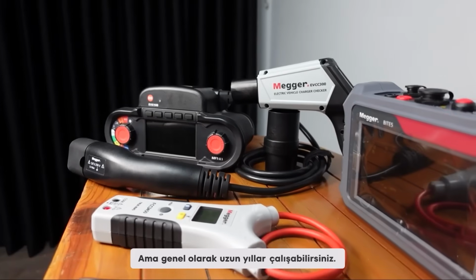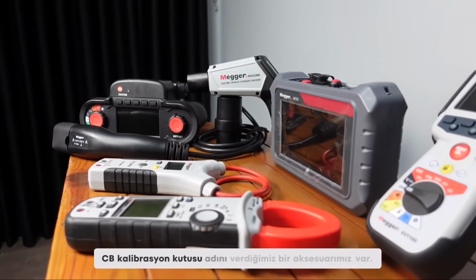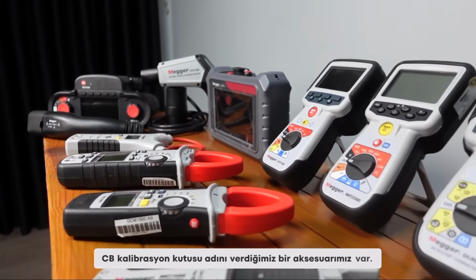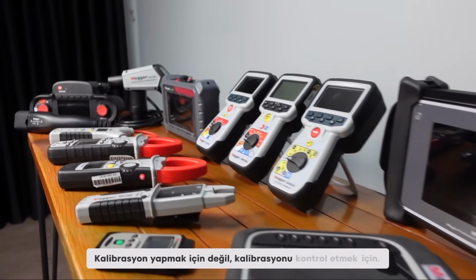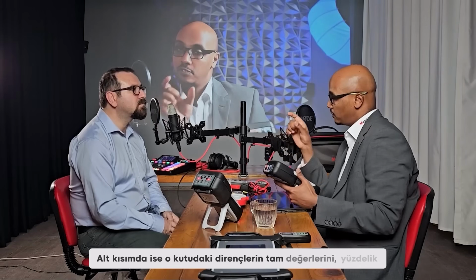Okay. You can trust these devices, Megger devices, and you can use it without any calibration. Maybe only just test it. Just check. But in general, many years you can work properly. So we have an accessory called the CB calibration box. It's not for doing calibration, it's for checking the calibration. So we have a CB100, CB101, and different models. So with that CB box, it's a small box. You connect to it. On the bottom, we give you the exact value of the resistors in that particular box with the percentage tolerance. And then you do the measurement, and as long as the value is within the percentage tolerance for that value of the resistor, you're good.